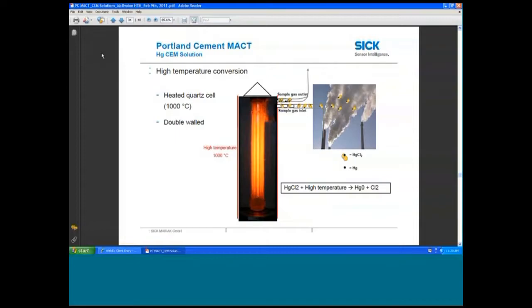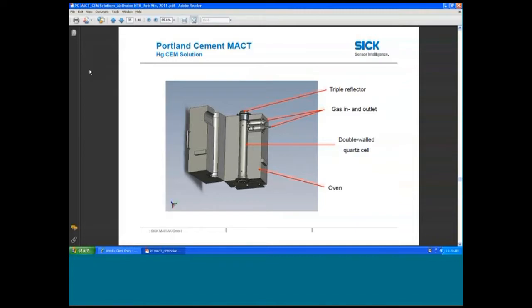Next slide. Here you can see a picture of what the internal cell looks like, heated. It's a double-walled cell, so we bring the gas on the outside wall, do the conversion, and then we put it into the internal area of the cell where the measurement takes place. Next slide. And here's what it looks like in practice. The oven surrounding it is actually as much for protection as anything, where it's much hotter in the middle, cooler in the outside, so we can get the temperatures in a safe way without compromising safety.